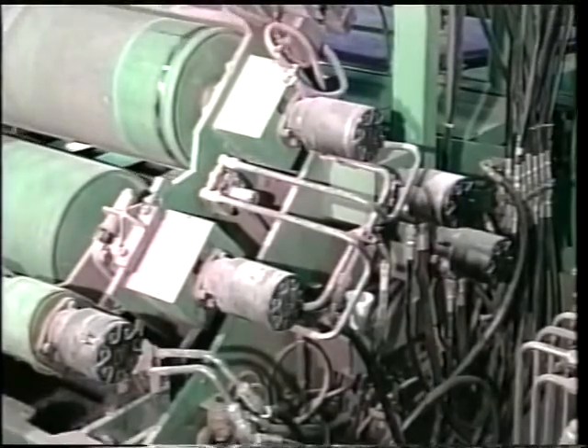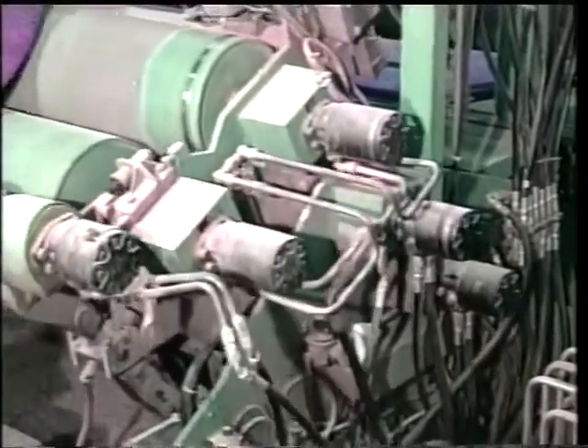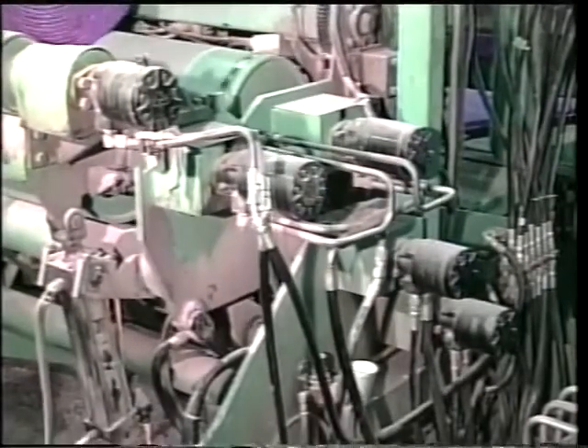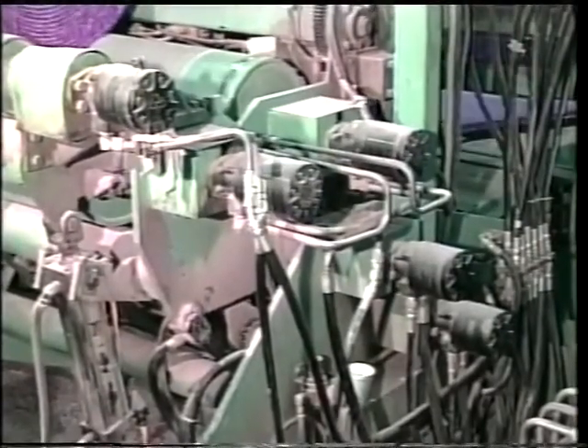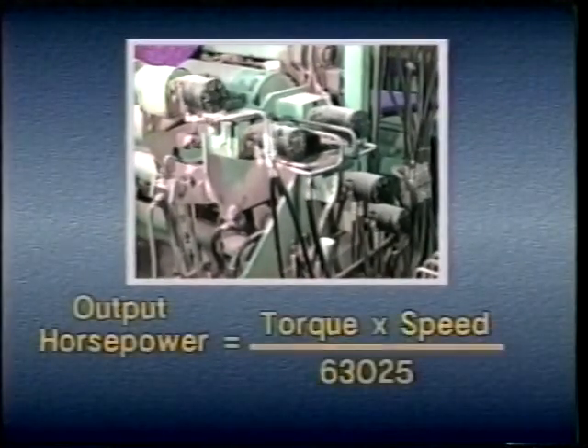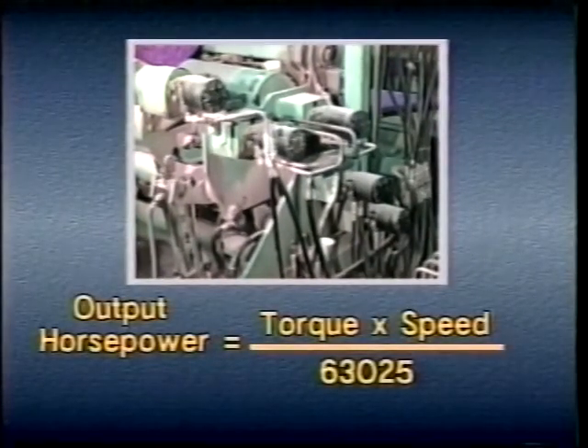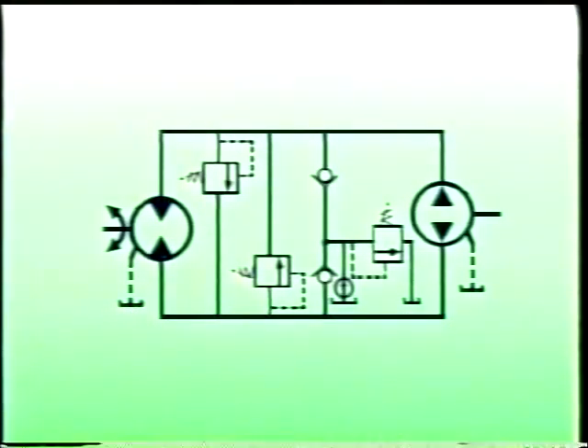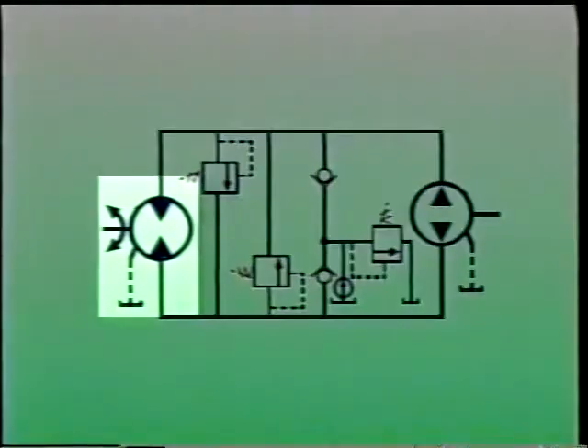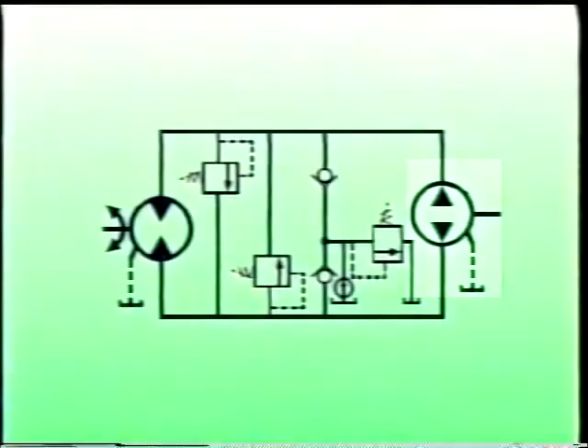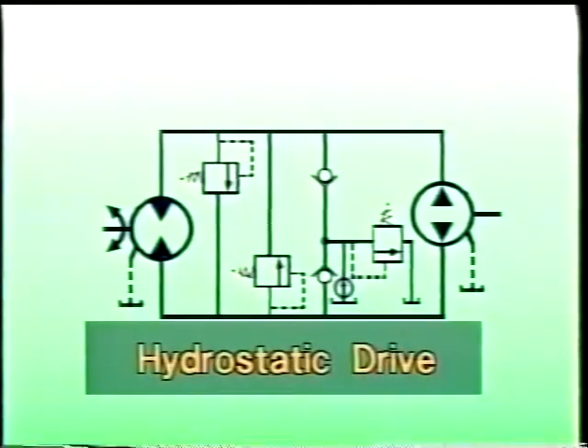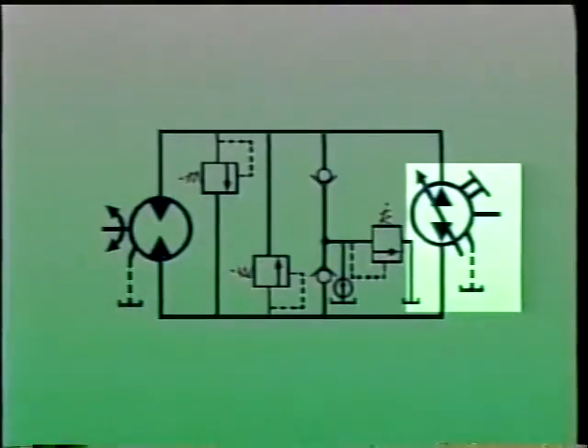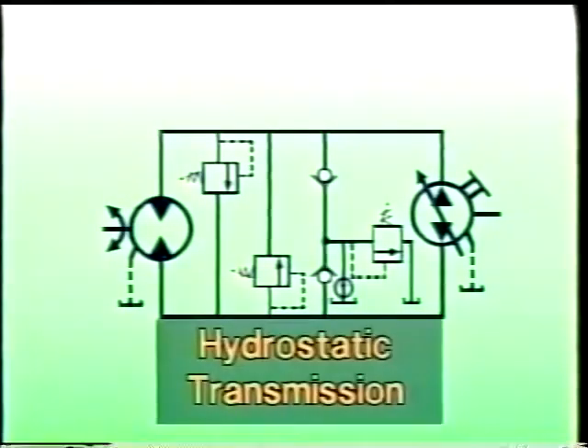Control of the torque and speed of hydraulic motors also permits control of horsepower, because torque and speed determine the work a motor can do in a given amount of time. Output horsepower is equal to torque times speed divided by the constant 63,025. When motors and pumps are combined in systems, it is possible to control torque, speed, and horsepower. If both the motor and the pump are constant displacement, these systems are usually referred to as hydrostatic drives. If either component has a variable displacement, the system is sometimes called a hydrostatic transmission.